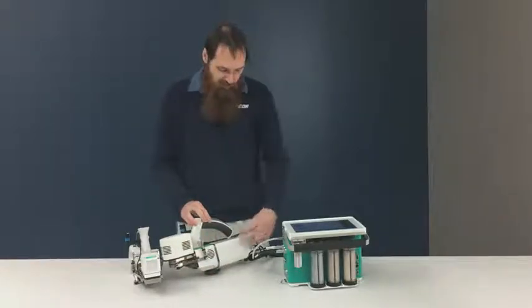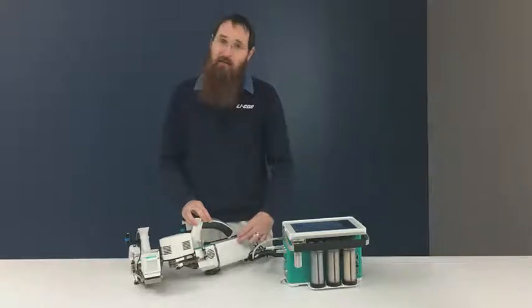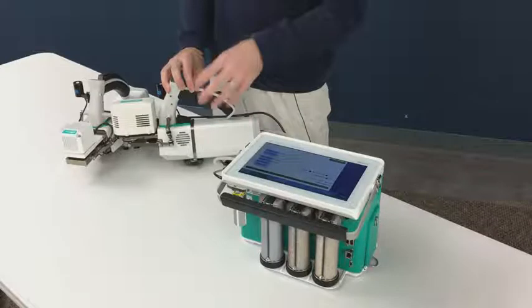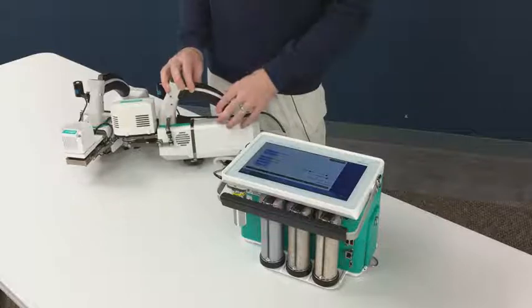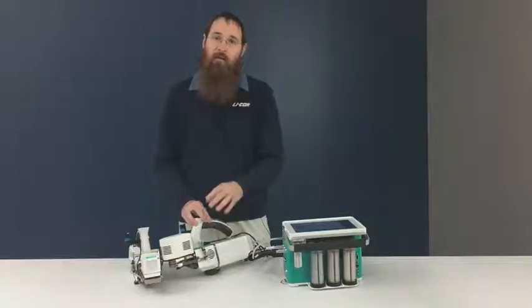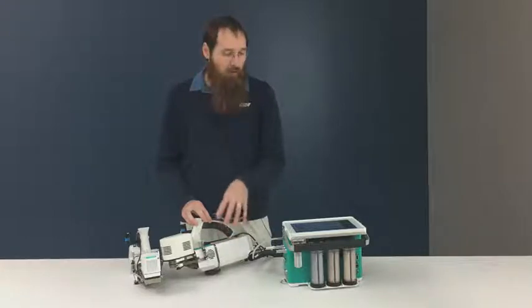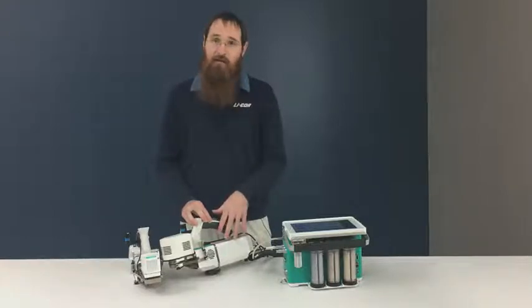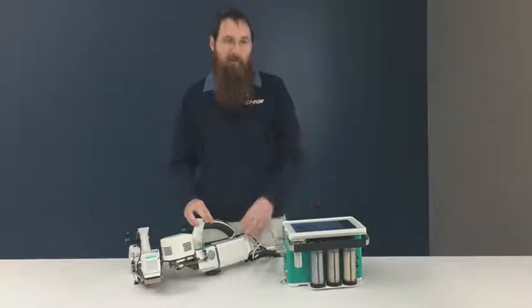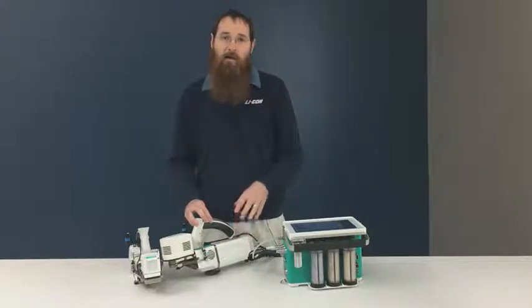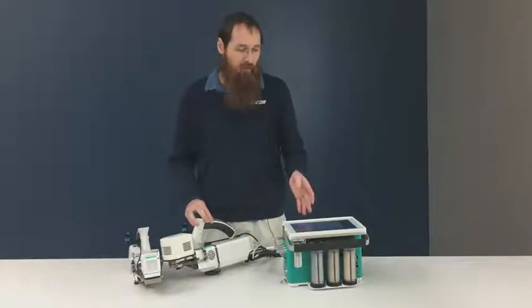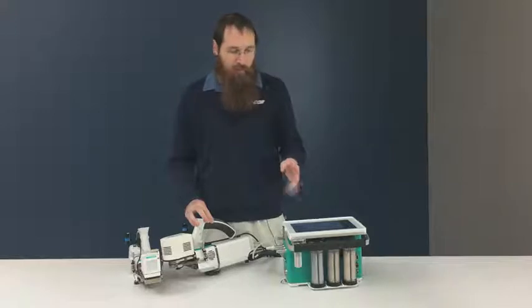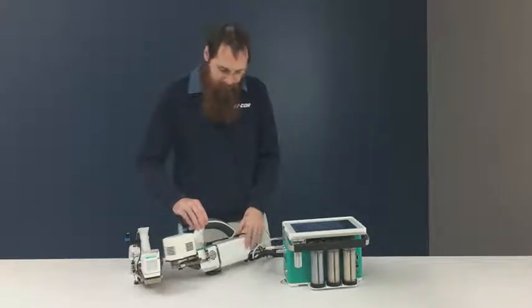Once this tube enters, there's a short section of plastic tubing, and then everything is metal and O-ring sealed from that point forward. That means the flow split and flow control are all embedded inside the sensor head. In a moment, when I go through environmental controls on the instrument, I'll show you what that flow path looks like and some of the cool things we do with it.